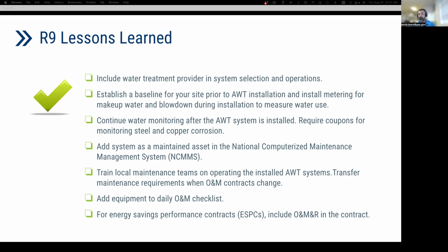David had mentioned establishing a good baseline. We spent several months monitoring, checking levels, and we wanted to make sure we knew exactly how much water was being used, how much energy was being used. That way, after we installed the equipment, we're able to validate the success of the equipment. It's been mentioned several times that it's important to add this to some sort of maintenance record. Like we have a CMMS where we track all of our inventory, we create PMs and work orders with this system. We made sure we added this equipment to that system right away. That way, PMs can be generated on a regular basis, and we can make sure that our equipment is being maintained properly.